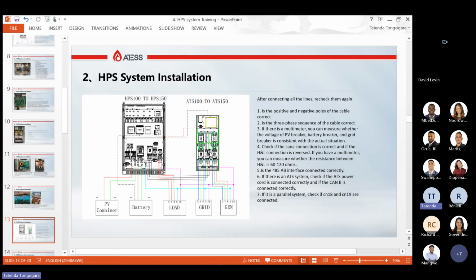HPS installation. After connecting all the lines, you just need to check polarity and the 3-phase sequence. Our HPS phase rotation should be clockwise. So your AC input should be clockwise, your generator input should be clockwise. If the site's machines are running anti-clockwise, then you just connect the load in the anti-clockwise direction, but everything else you have to connect in the clockwise direction for it to work. If you connect your grid anti-clockwise, your HPS will not accept it.